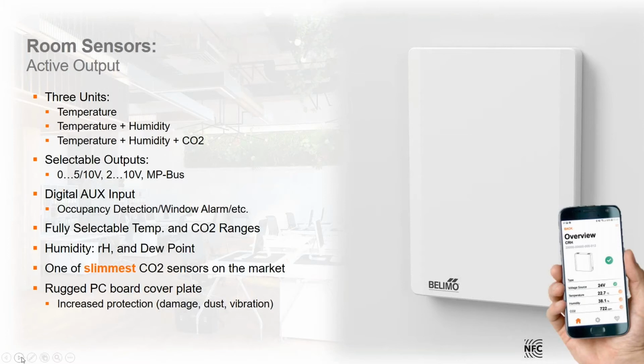Through NFC, as you can see here at the bottom right picture, all of the outputs are independently selectable. So you could choose anywhere at 0 to 5 volts, 0 to 10 volts, 2 to 10 volts, MP bus, and they're all independent of each other. So you can go into the app, and for example, if you have the temperature and humidity sensor, you could do a 0 to 5 volt temperature output, and you could also have an MP bus humidity output. They're all independent of each other.